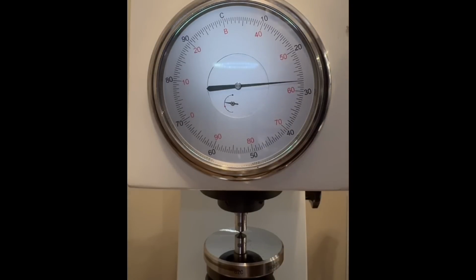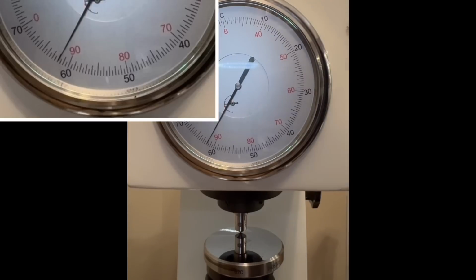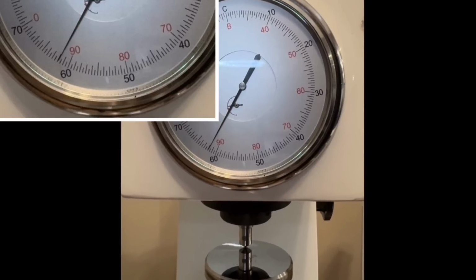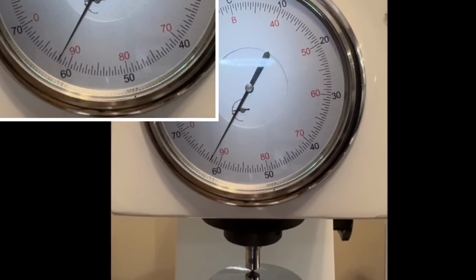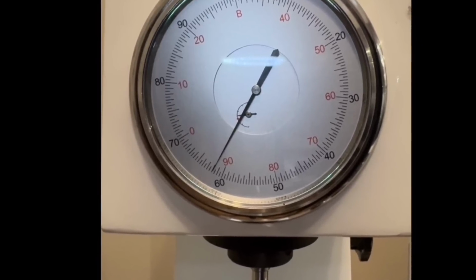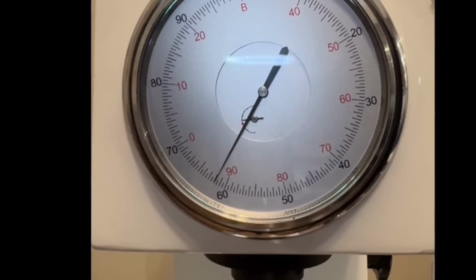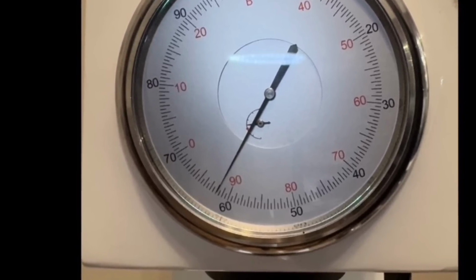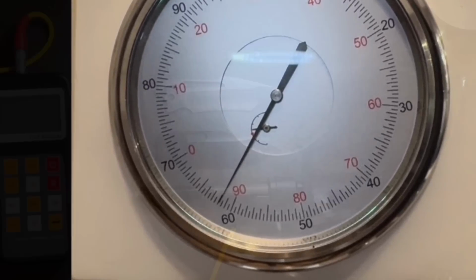All right, the time is up. Let's see what it reads. And we got a 61.9. As I said, this block is NIST certified independently, and the tester itself came certified from the manufacturer, which is good until September 2025.